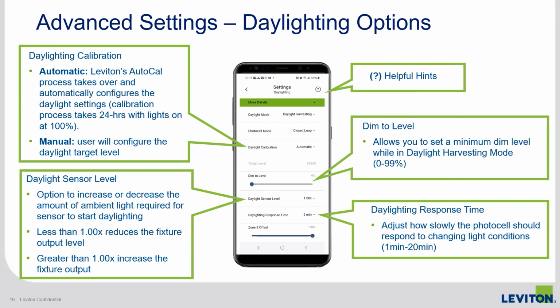For daylighting calibration, you can select the device to do it automatically or do it manually. For automatic calibration, the sensor will use Leviton's AutoCal process, which will hold the lights on for 24 hours to calculate the target value, which should be based on artificial lighting only. If manual calibration is selected, you can select the target value yourself. The page will display the current light lux value that the sensor is seeing. Once the target is set, the daylighting will kick in instantly, no need to wait 24 hours.